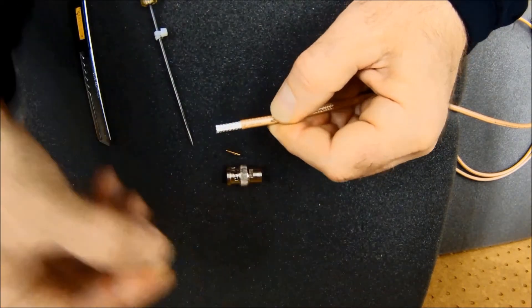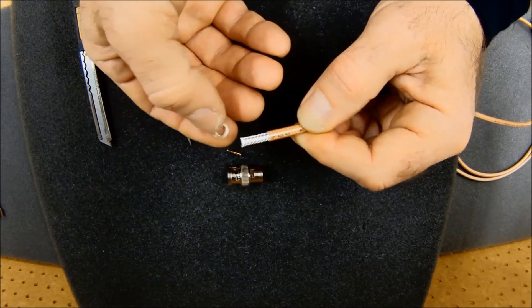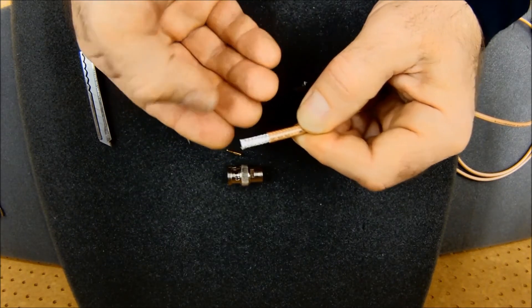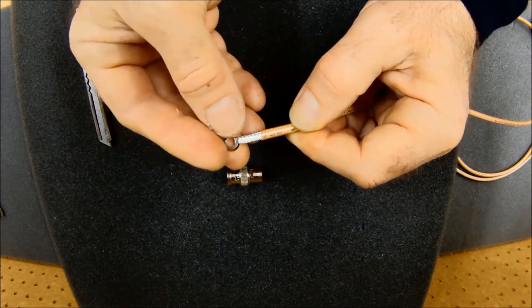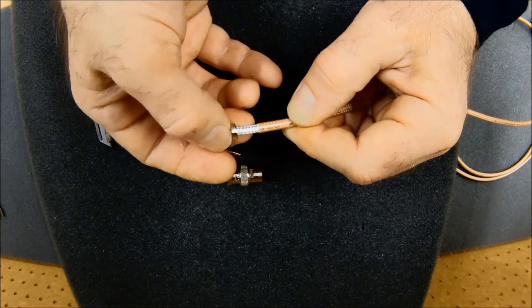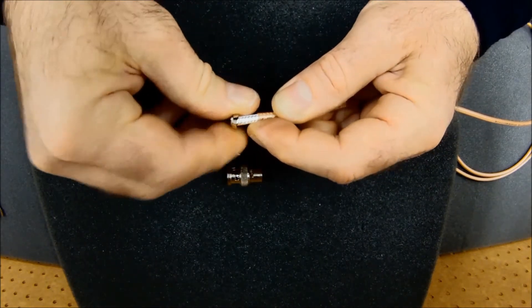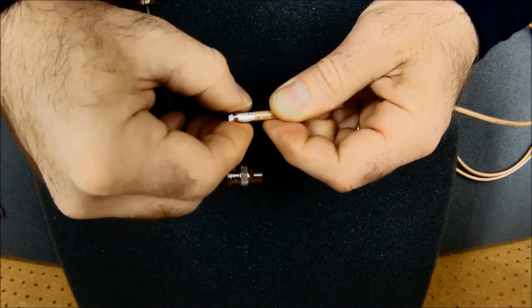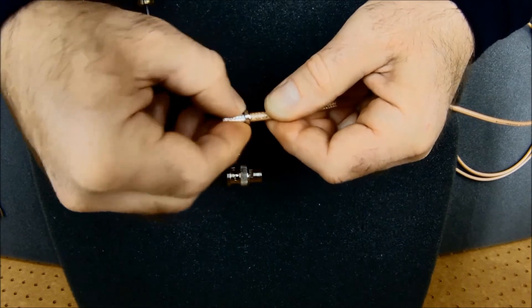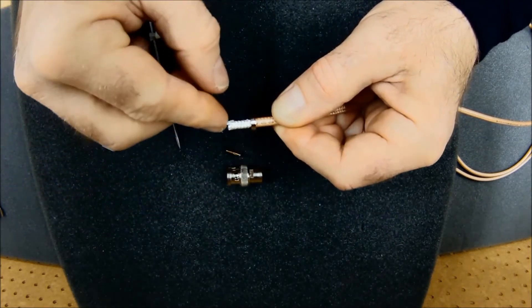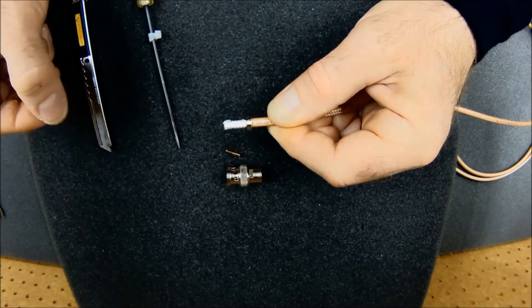At this point, I'm going to take this shoulder washer. It has a little shoulder on the inside and it's tapered, pointing in the direction that it goes into the connector. And I'm going to slide it up on my coax. I like to do this before the braid starts to get all frayed out. It's going to sit right there.